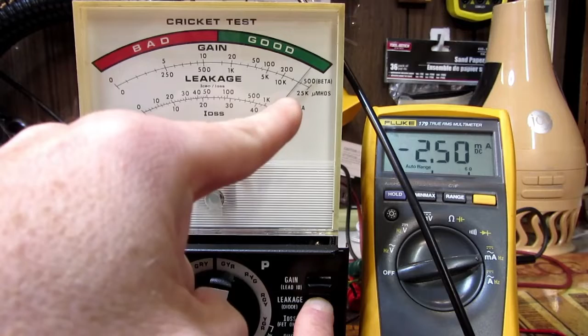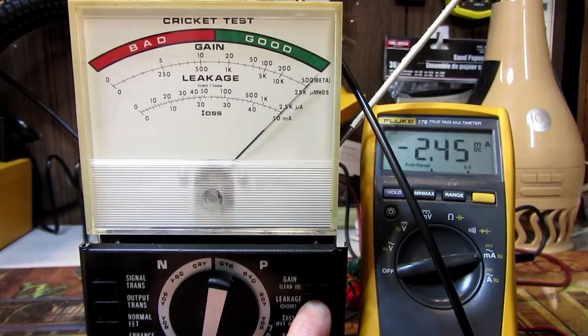Okay, as you see, when I went back to recheck the first calibration point, it's off. So now we have to tweak that outside pot until we get it back to where we want it to be, full scale. Okay, it's redialed back in, so now we have to recheck the 250 microamp range. Out, in at 250 microamps, and you can see that it's almost perfect here, just about a hair of a needle, and I'll go ahead and give that a slight adjustment. The 250 microamp adjustment is the second one in from the right side.